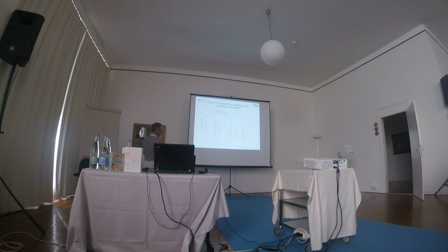And just so you can see the results, imagine the red line is the real flow trace that we are recording with the data logger that we have developed, in which we store the time of occurrence of the pulse. And the green line is how that flow trace would become if we store the number of pulses every 10 seconds. And you see that the differences in the flow traces are quite significant.